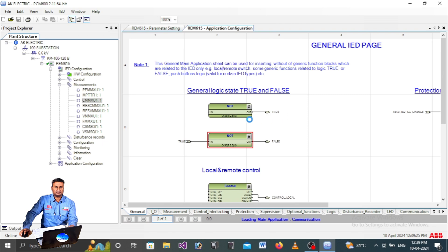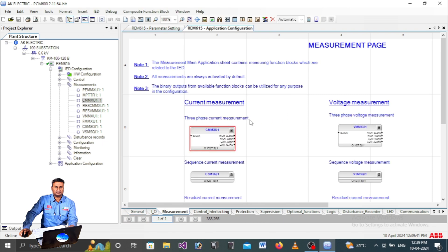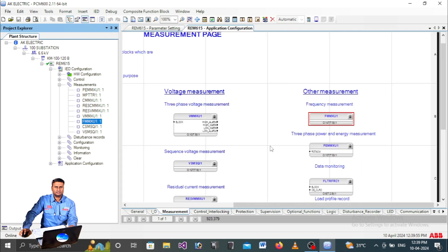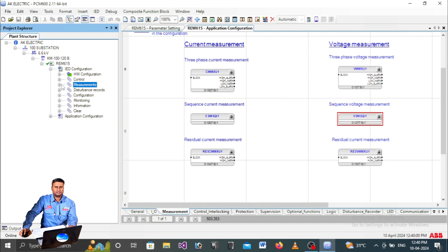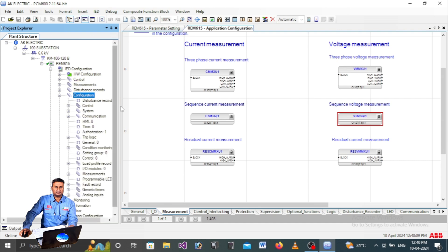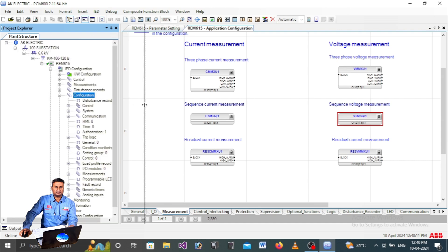In the application configuration you can see the three-phase current measurement block (CMMXU1), the voltage block for three-phase voltage measurement, and the frequency block. This is how everything is organized - all under IED configuration. To see CT ratio and VT ratio, click Configuration and go to Analog Inputs.